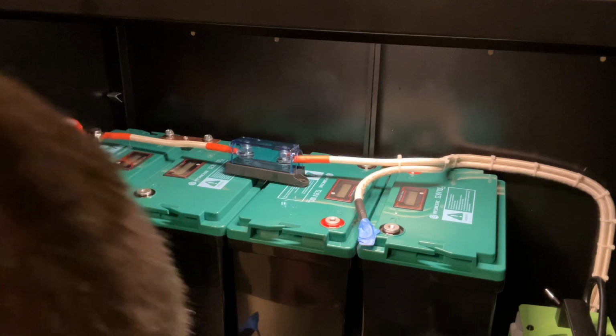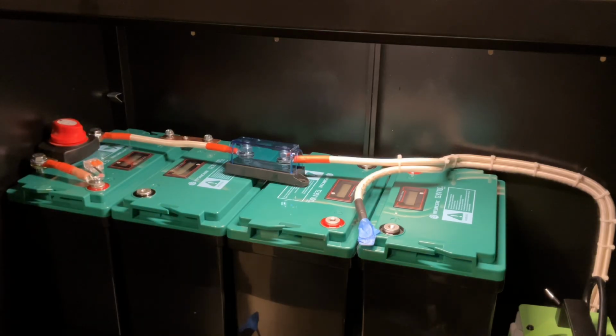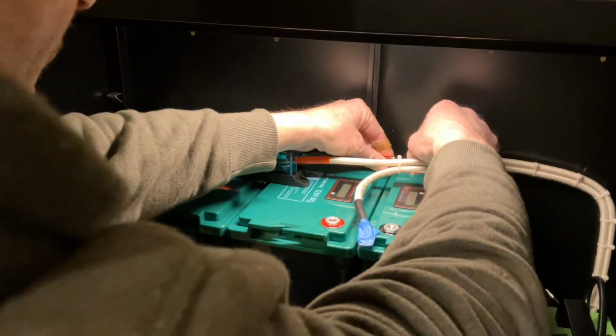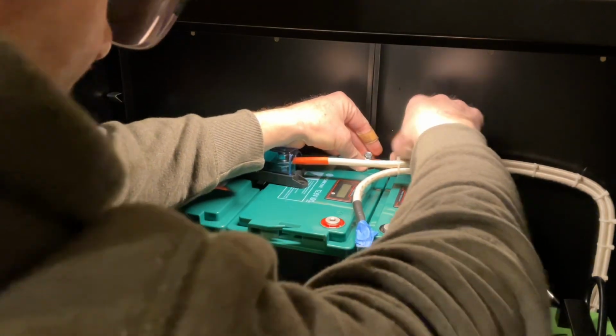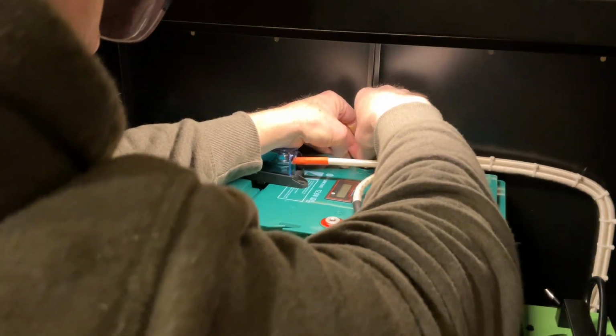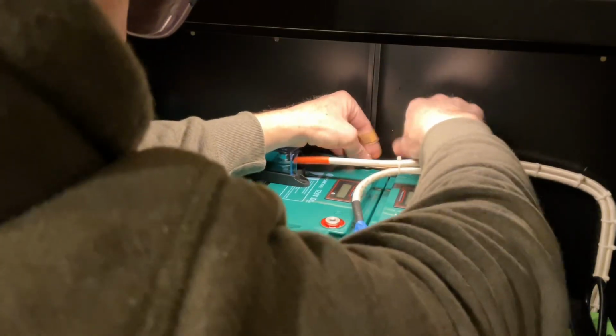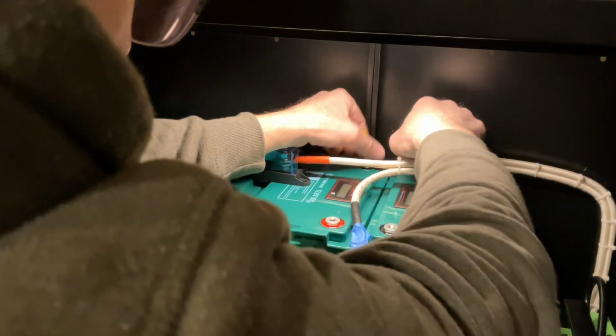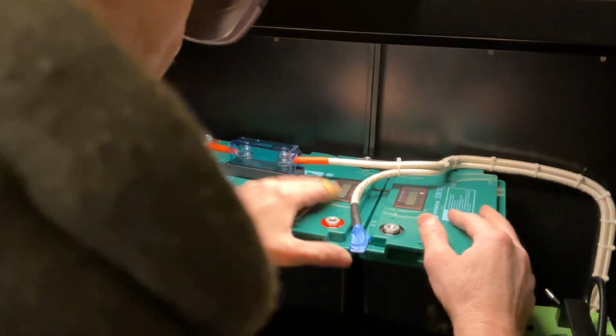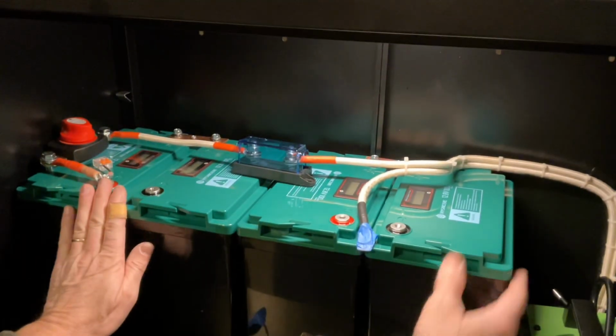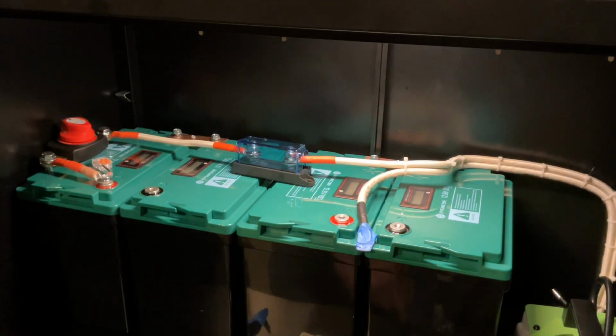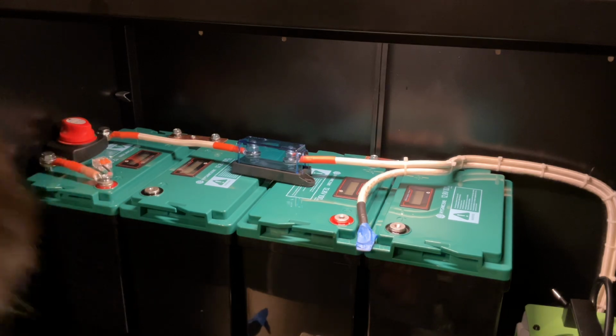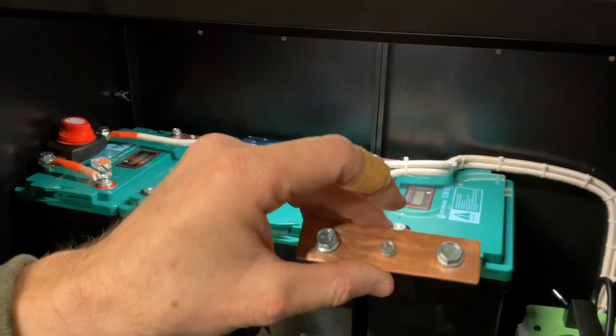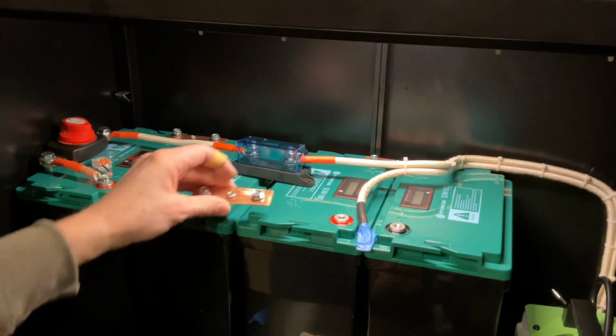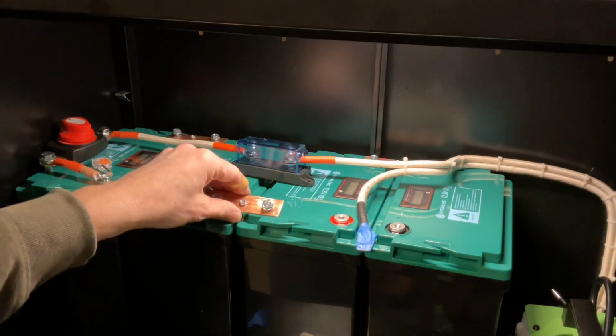That's going to be the configuration going forward. Fortunately, the bus bars from the previous battery bank configuration still reach, because when I measured the distance with the battery packs oriented this way versus before, they actually still reach, end to end or sideways. So right now these two bus bars go in there, and the third bus bar is no longer needed—I have to make a longer one instead that'll span this distance.